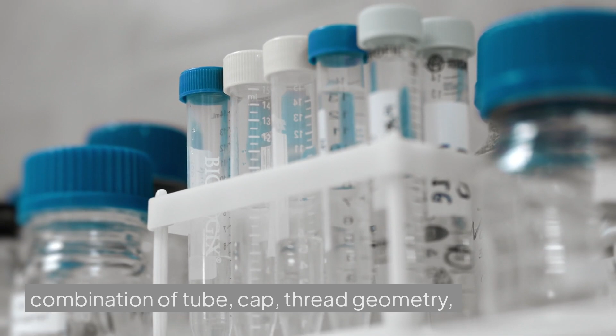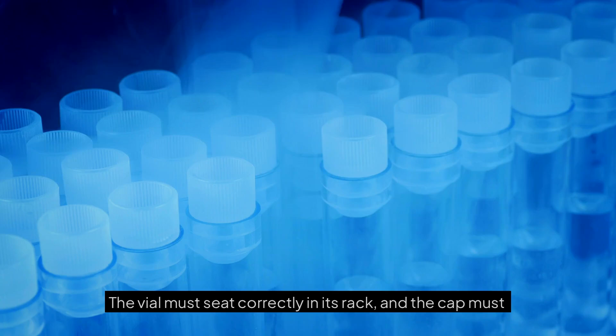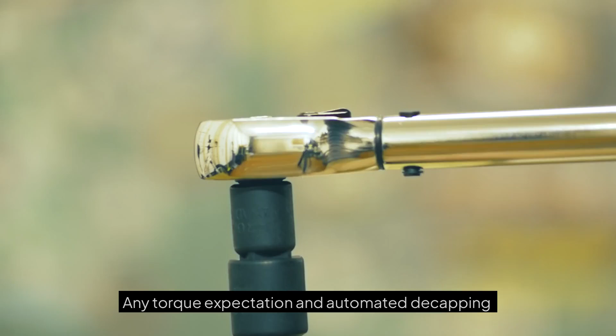Closure qualification begins with the exact combination of tube, cap, thread geometry, rack, and handling method. Internal thread and external thread designs may support different workflows, but neither format is universally preferable. Operators must be able to close the vial consistently while wearing protective equipment. The vial must seat correctly in its rack, and the cap must remain manageable after cold exposure. Any torque expectation and automated decapping requirement should also be defined.